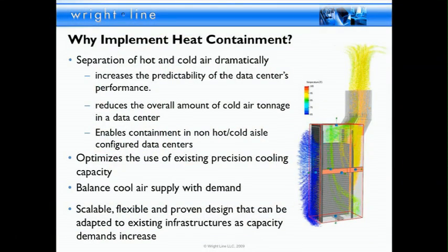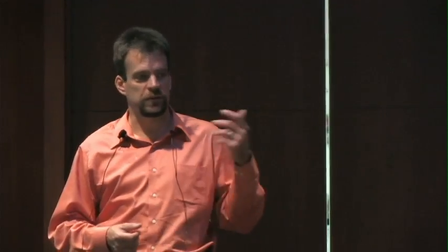So why implement it? All those strategies for maintaining that front to back airflow and for exhausting the air out of the rack give you a high separation between hot and cold, and will dramatically improve your capability and predictability in your data center. And it reduces the overall amount of air that you need to supply to cool the IT equipment. On average, if you add up the CFM being supplied by your CRAC units and the CFM required by your IT equipment, we see a 130 to 140% difference. That's a significant difference, meaning that 40% is oversupply. That's available to either be more efficient in your supply or handle additional load without radical changes to your data center. And the end result is balancing that supply and demand.